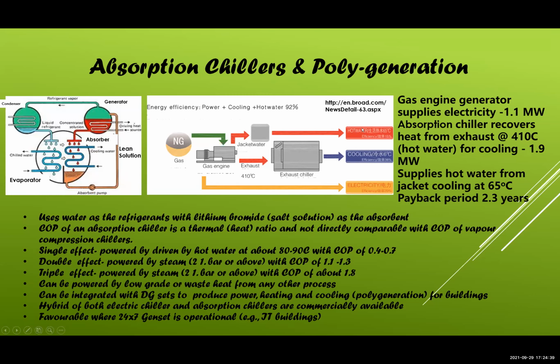And there are multiple possibilities. And this is now becoming very popular. And there are two major manufacturers, one in China, Broad, another in India, Thermax. They sell bespoke. And please remember, absorption chillers are not packaged to the extent of mechanical vapor compression chillers. They're all bespoke because you have to decide whether it is going to be exhaust gas driven, hot water driven, or steam driven, high pressure steam driven. Accordingly, they have to design, but you can buy up to 1,400 tons in one chiller.